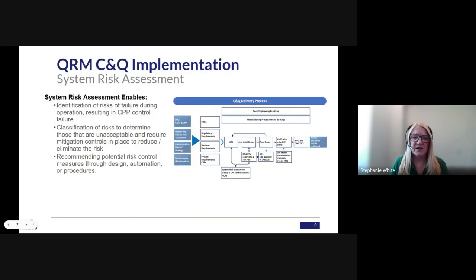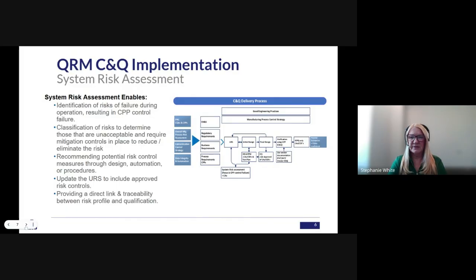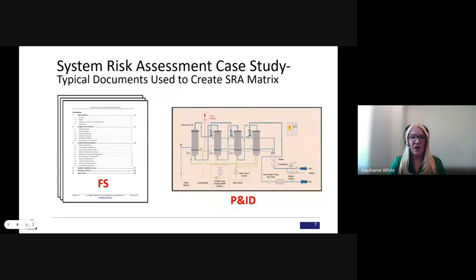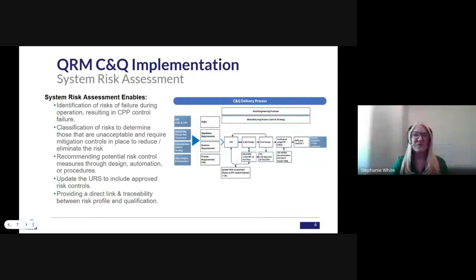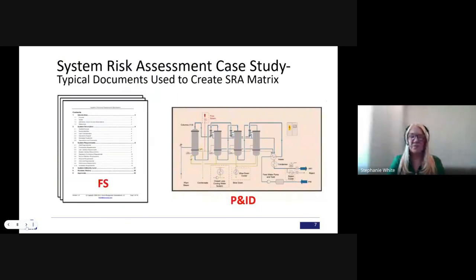Recommend potential risk control measures through design, automation and procedures, which I just mentioned, and I think there's another one. And then if you find after you do your risk assessment that you are missing requirements in your URS, so maybe you have a design element that was not covered in your URS, you would need to go and update your URS. So it's very imperative not just to do the risk assessment, but to map it back to every single requirement in your URS that has quality impact. Next slide, please. Providing a direct link and traceability. So I just mentioned that. So yeah, providing a direct link between your risk profile and your qualification.